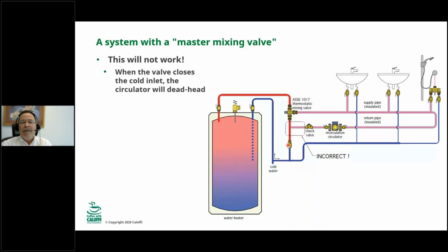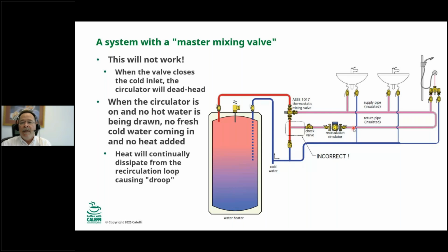Now let's think about this. If this circulator is running and there's no water being drawn at the fixtures, there's no cold water coming into the system. So even if this valve didn't close, if we just circulated this water around and around and around here, eventually it's going to give up heat to the space, and that loop is going to cool off. That's called droop, recirculation droop. And we're not going to have any hot water coming into the thermostatic mixing valve. Why? Because there's no cold water going into the tank. If you don't have any cold water going into the tank, you won't have any hot water coming out of it. Okay, so that's one condition called droop. So the first person in the morning that opens a tap is going to get water that's colder than they expect.